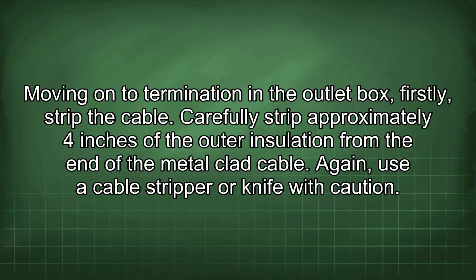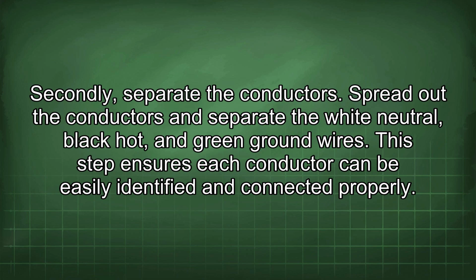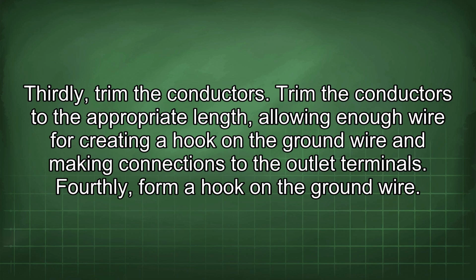Moving on to termination in the outlet box, firstly, strip the cable. Carefully strip approximately 4 inches of the outer insulation from the end of the metal-clad cable. Again, use a cable stripper or knife with caution. Secondly, separate the conductors. Spread out the conductors and separate the white neutral, black hot, and green ground wires. This step ensures each conductor can be easily identified and connected properly. Thirdly, trim the conductors. Trim the conductors to the appropriate length, allowing enough wire for creating a hook on the ground wire and making connections to the outlet terminals.